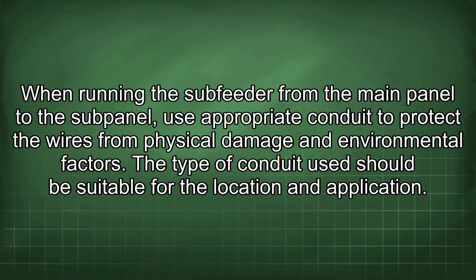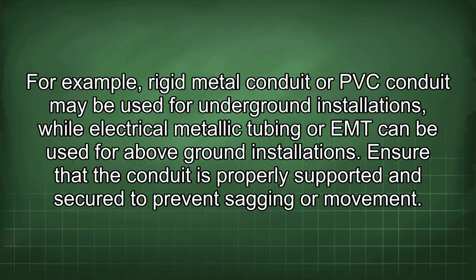The type of conduit used should be suitable for the location and application. For example, rigid metal conduit or PVC conduit may be used for underground installations, while electrical metallic tubing, or EMT, can be used for above-ground installations. Ensure that the conduit is properly supported and secured to prevent sagging or movement.